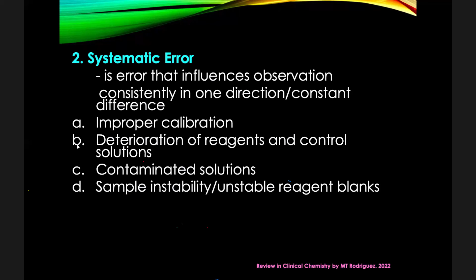When you expose the sample to direct light, and that is for photosensitive, and that is for bilirubin or any other photosensitive analyte measurement, that is systematic error. Bakit? Alam mo, in-expose mo sa light. That is predictable error. Unstable reagent blank, leaky ion selective electrode. What is ISE? Ion selective electrode is an instrument for measurement of electrolytes.